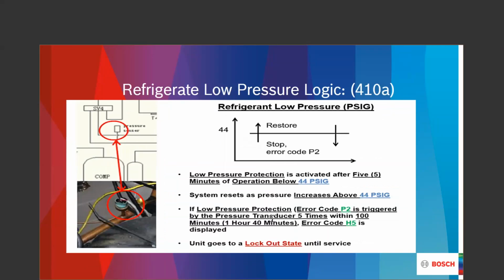Low pressure. We're looking at a 44 psi differential of low pressure. Anytime my system would see below 44 psi and I'm there for 5 minutes of operation, I am going to start the process. I may get out there and see a P2. The P2 is an indicator that I've got something problematic going on. If that P2 stays there basically for 5 times within that 100 minutes (1 hour 40 minutes), then we're going to have an H5 fault code. That H5 fault code is going to lock the system out.